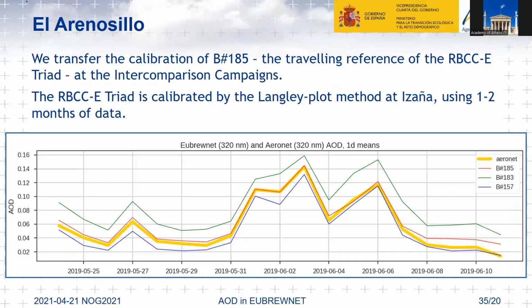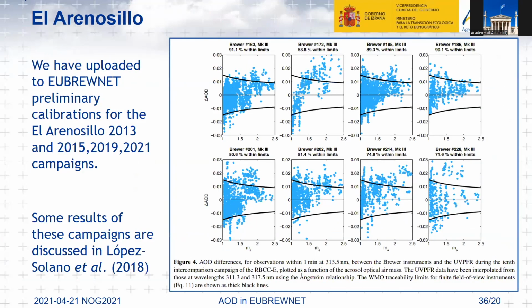I go fast. This is an example of how we transfer the calibration for the 185, that is a fully calibrated Brewer, and we transfer the calibration to the campaigns. This is, as you see, the three instruments that we have. And then these are the results, what we can have. So for some of the instruments, the agreement is pretty good, but for others, it's not so good. Mainly, we're investigating that.